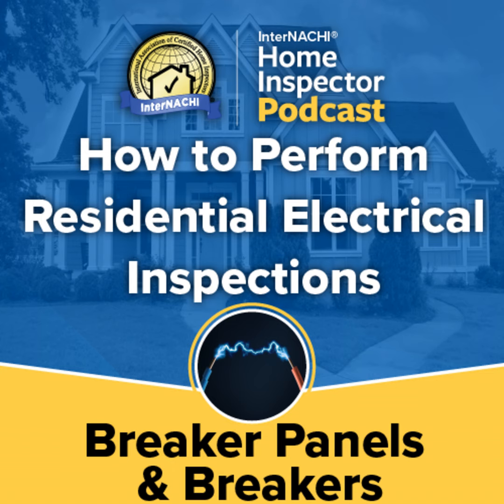These are made by Square D and Cutler Hammer. These should not be confused with double-tapped breakers, where more than one conductor has been incorrectly connected to a single breaker. GFCI breakers. Ground fault circuit interrupter, GFCI breakers, are one of the ways to protect circuits and people from ground faults. Not all circuits are required to have GFCIs, and in many homes, the locations that require this protection have their own GFCI receptacles.